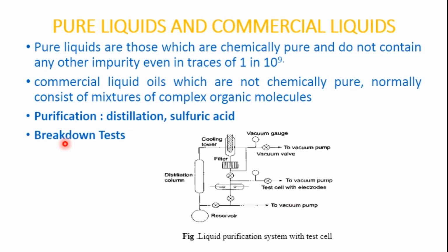Then we have a breakdown test. We use different methods to conduct the breakdown test. We are expecting around 50 to 100 kV. Our requirement is 5 megavolt per centimeter, but we make it around 50 to 100 kV. The electrodes used for the breakdown are generally 0.5 to 1 centimeter in diameter and are spaced at 100 to 200 micrometer.